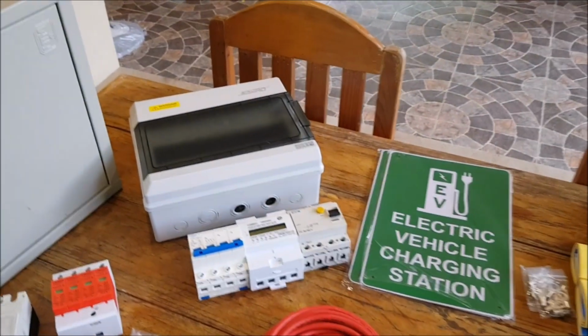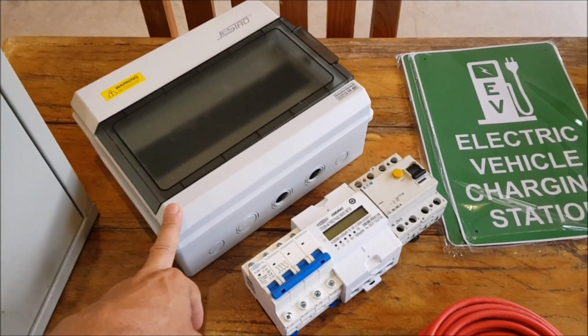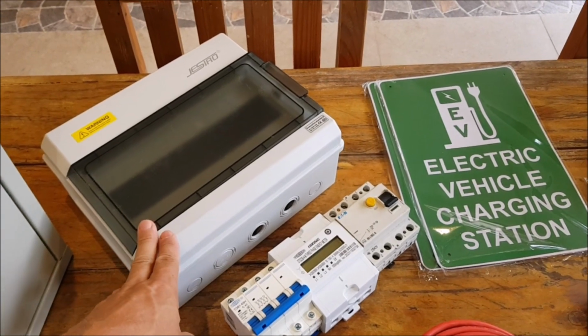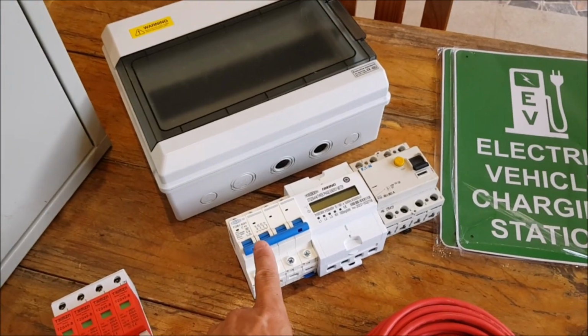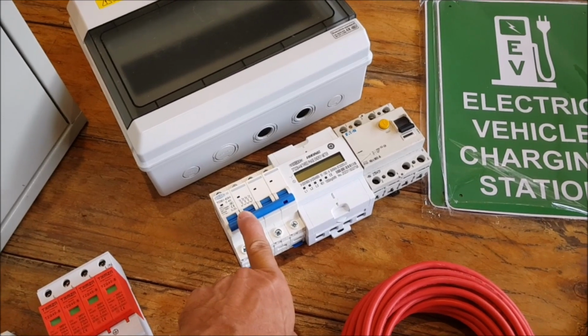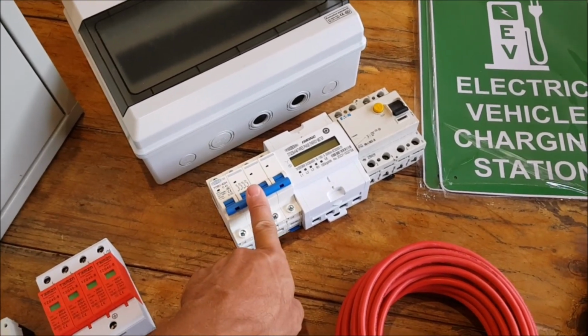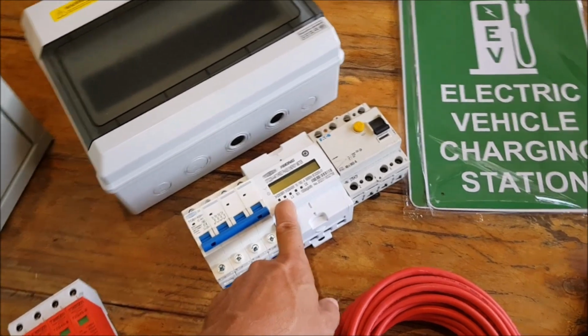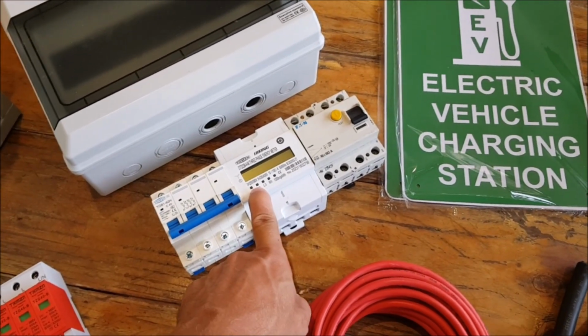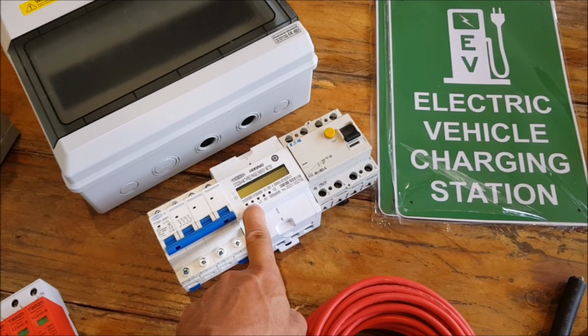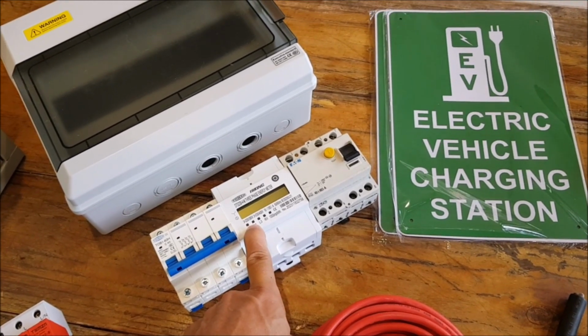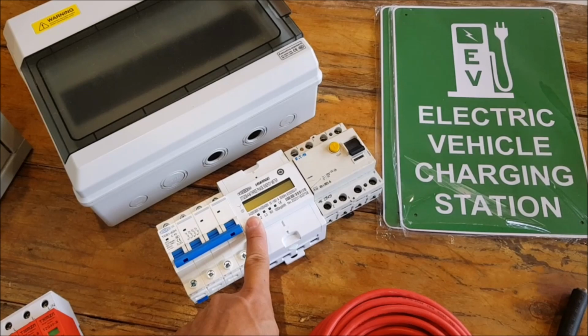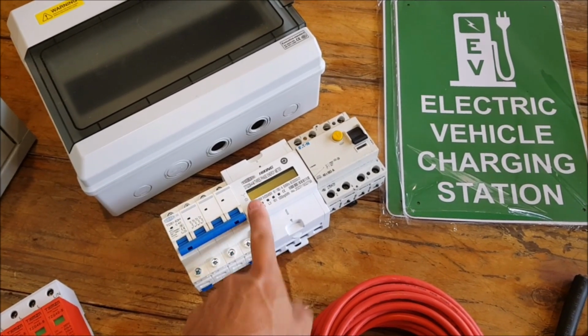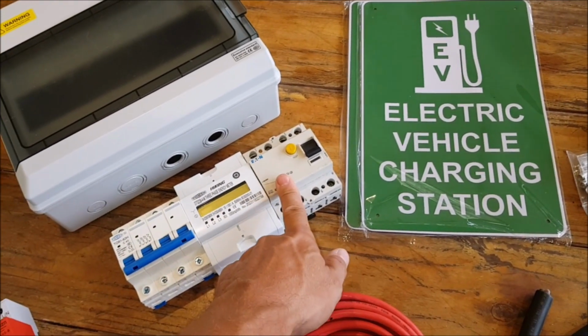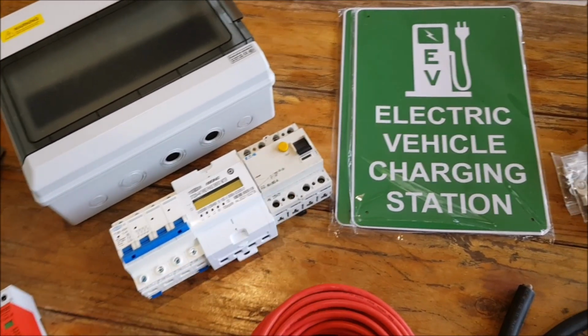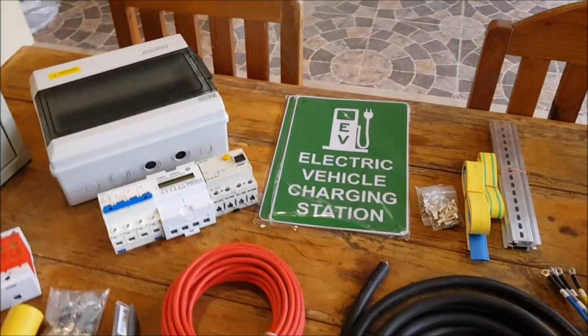All this will be connected to an extra load center. So here, this box will fit the main switch. This will be a 40 amp 4-pole main switch. Then there will be a meter, a 3-phase meter, because these cheap stations do not log, of course, what they do. And once you finish, nobody knows how much power was actually taken. So a meter and then a 3-phase RCD which will watch over the station.